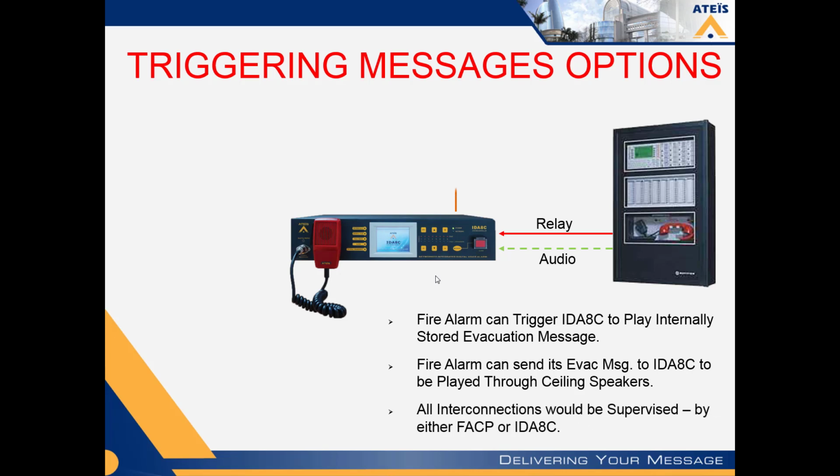Both of these connections, no matter which way you do it with the fire alarm or the ID8, can be supervised either from the fire alarm system or it can be supervised by the ID8 system. So if there's a break or a problem between, you'll get some supervisory or fault annunciations, and or both. So there's a bunch of different ways. So no matter how stringent your local authority having jurisdiction may be, we have a way that we can supervise it that should make the fire marshal or your safety officer happy.